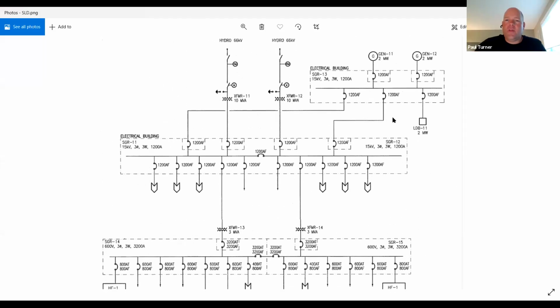So back up here at the top, I also mentioned that we have a diesel genset backup. We have a pair of 2 megawatt diesel gensets, and these would normally be left off and on standby in case there should be a disruption to the 66 kV power. So let's consider the scenario that one of the 66 kV feeds is disrupted, and the utility no longer provides that power to the system. In that case, the incoming breaker to switchgear 12 would be open, and you can continue powering the entire plant off the second 66 kV feed by closing the tie breaker of the switchgear. That would energize the entire 15 kV bus off of the one 66 kV feed.